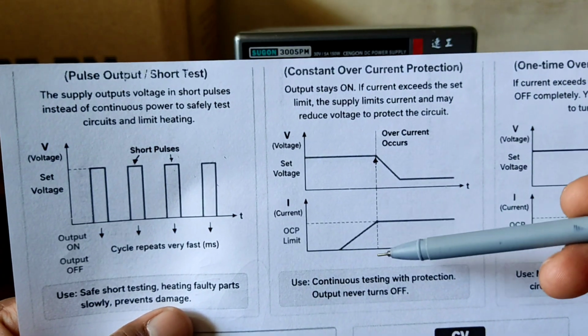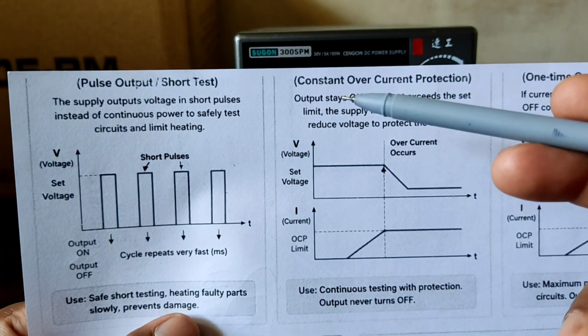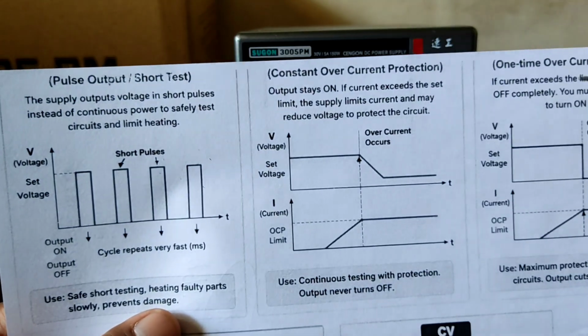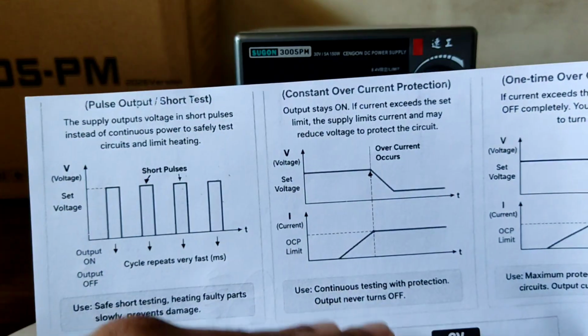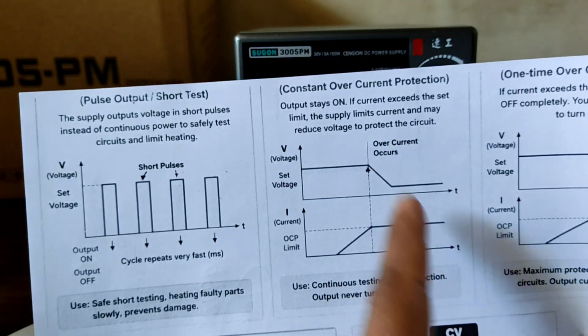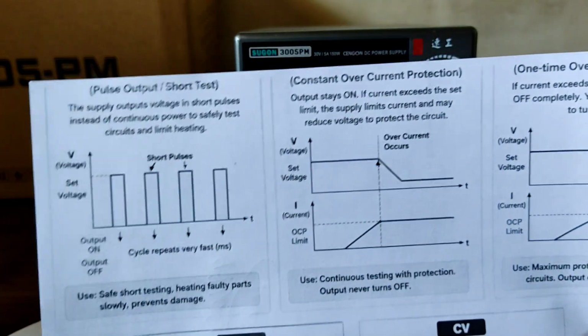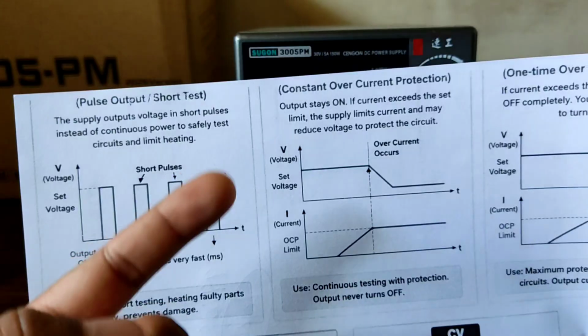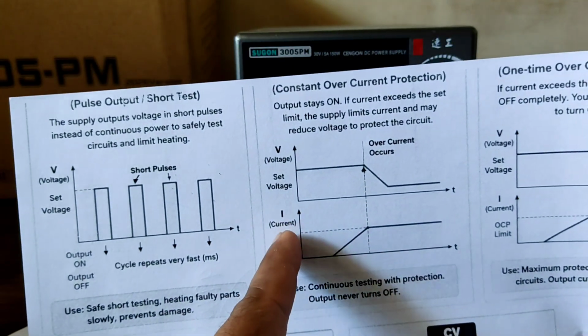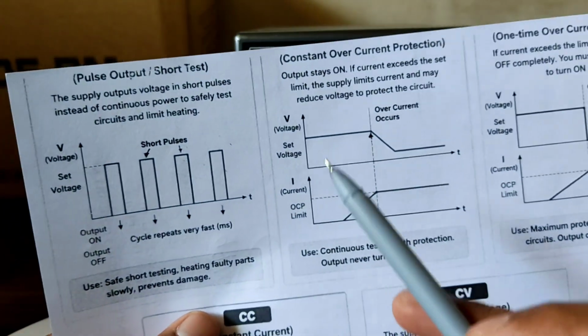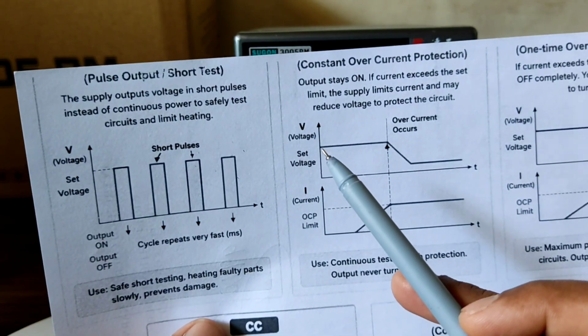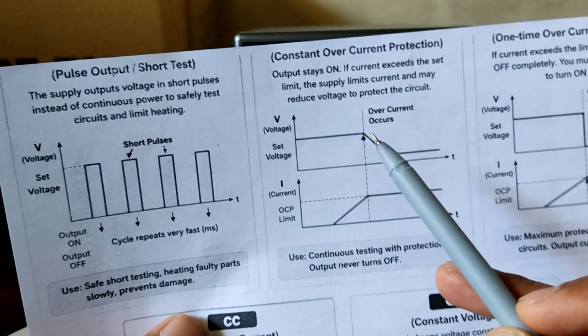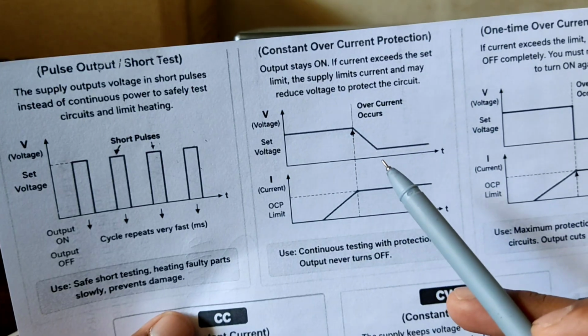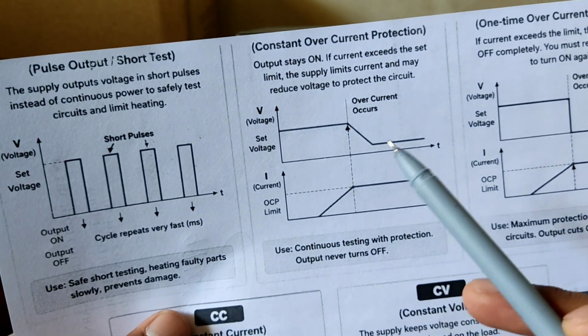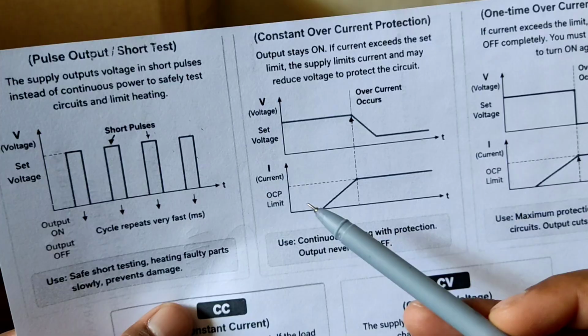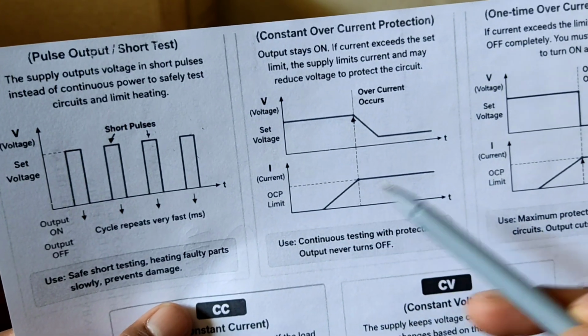Consider this dotted line as a fault - that time this triggers, meaning it will drop the voltage. Whenever you find a short, voltage will drop from the set level and current will increase from lower to the set level. Here we set it to 10 volt. Whenever a short is found, the voltage will drop and current will increase, up to the set point - the set limit it will increase.